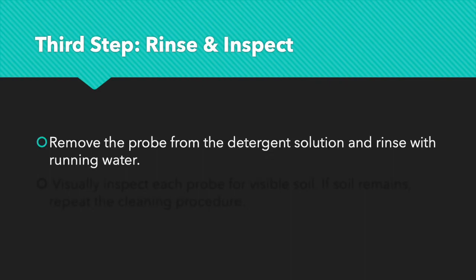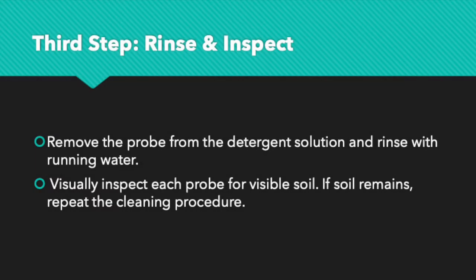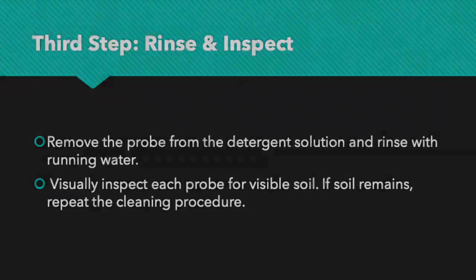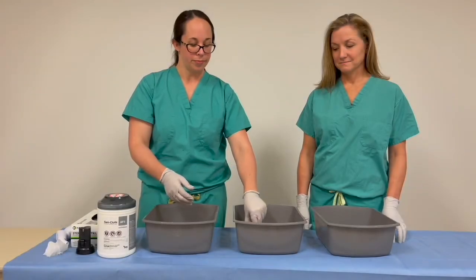The third step, rinse and inspect. Remove the probe from the detergent solution and rinse with running water. Visually inspect each probe for visible soil. If soil remains, repeat the cleaning procedure. The fourth step is a long soak.